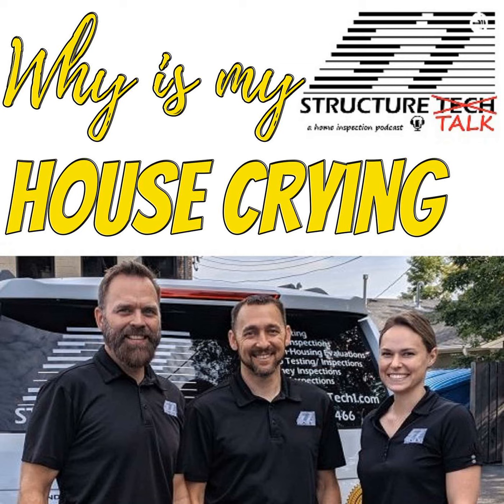Bill, just think about it—a house that's really old and leaky is going to have a more extreme stack effect than a house that's more airtight and sealed. So there'd be a bigger temperature gradient from basement to upstairs in a leakier house, because you're losing more heat, and more heat out means more cold air in. It'll be much colder in the basement and much warmer upstairs in a leaky house versus an airtight one. And if it's really cold and dry outside, it'll be drier in the basement because of all that cold, dry air coming in, versus warm, humid air from the house leaking upstairs.